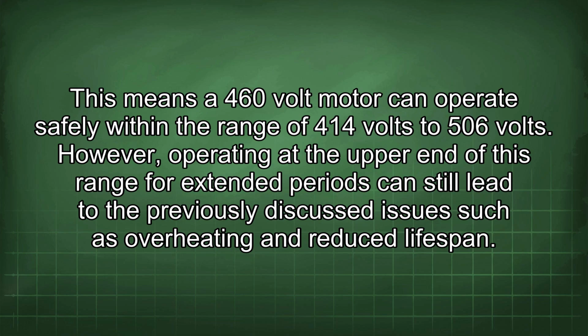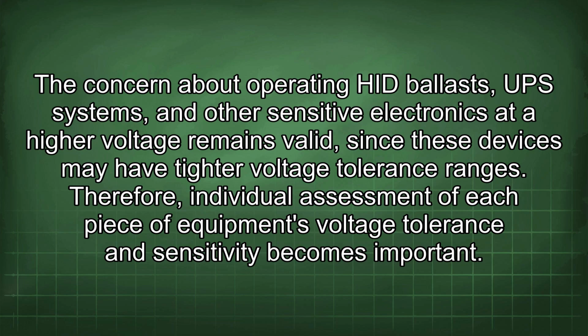However, operating at the upper end of this range for extended periods can still lead to the previously discussed issues such as overheating and reduced lifespan. The concern about operating HID ballasts, UPS systems, and other sensitive electronics at a higher voltage remains valid, since these devices may have tighter voltage tolerance ranges. Therefore, individual assessment of each piece of equipment's voltage tolerance and sensitivity becomes important.